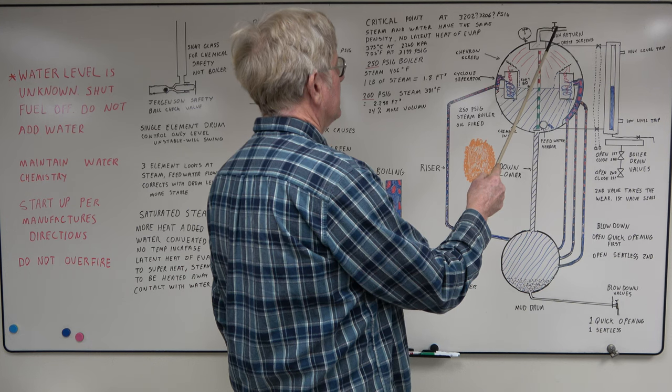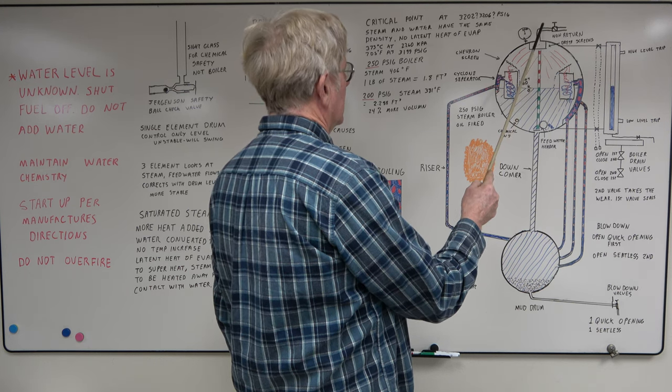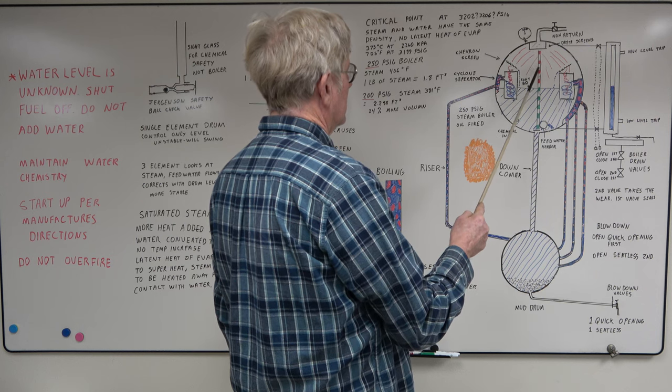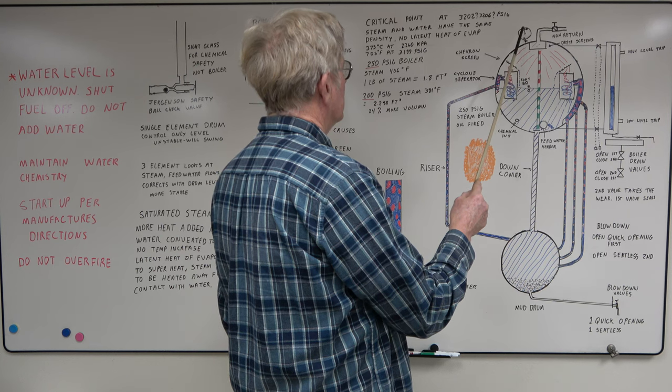Up here we have a non-return valve. It's a check valve with a hand-wheel gag. It keeps any steam from coming back in the boiler, which could be a catastrophic failure. And we have a pressure gauge maintaining, watching the pressure on the boiler.